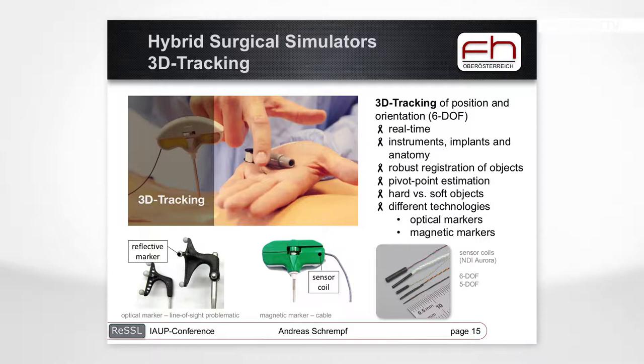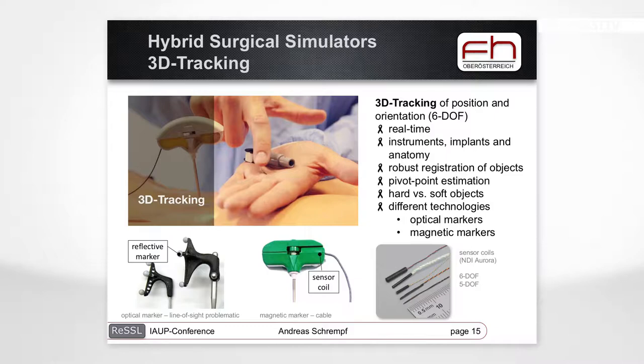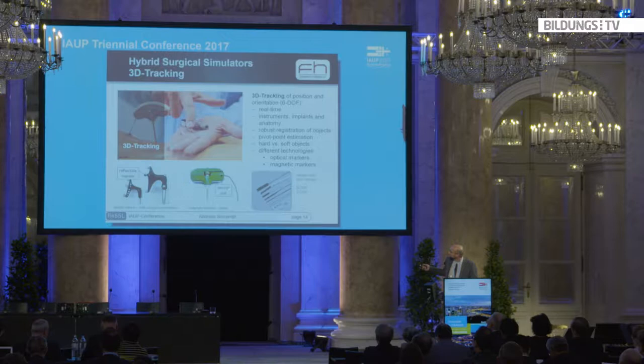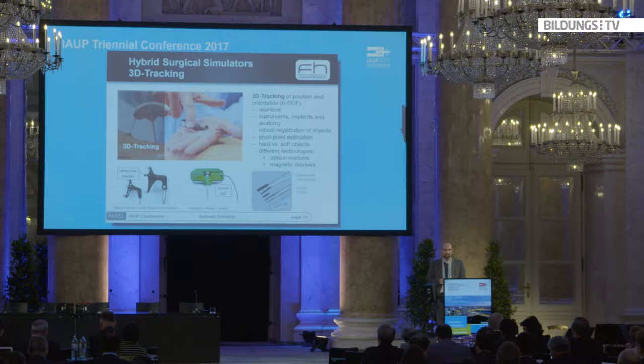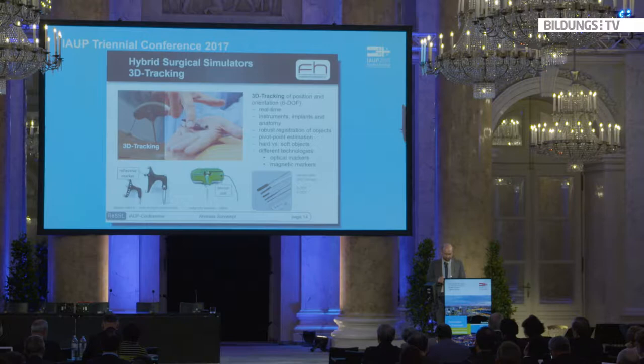For tracking real devices, we use either optical markers — a camera tracks the medical device by computing the position of the markers — or magnetic markers, which are small coils measuring position within a magnetic field. The sensor coil is very small, about 10mm long and 1mm in diameter, but requires a cable. The optical approach has the disadvantage that if something comes between the camera and the marker, the position is lost.